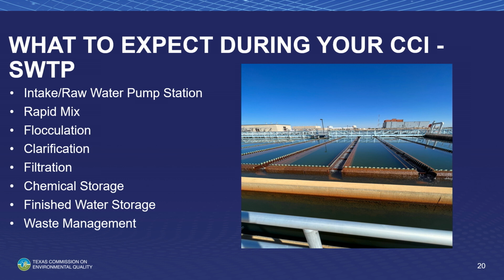So now that we've gotten through all the paperwork side of it, what to expect during your CCI. Like I said, I like to walk the flow of the plant. If we can start at the intake or raw water pump station, that's a good place to start. If not, then we're going to start where water enters your plant and any chemical injection points in between, going and looking at your rapid mix, flocculation, clarification, sedimentation, filtration. I'll want to look at all your chemical storage facilities, the finished water storage, and I'll also want to look at your waste management.